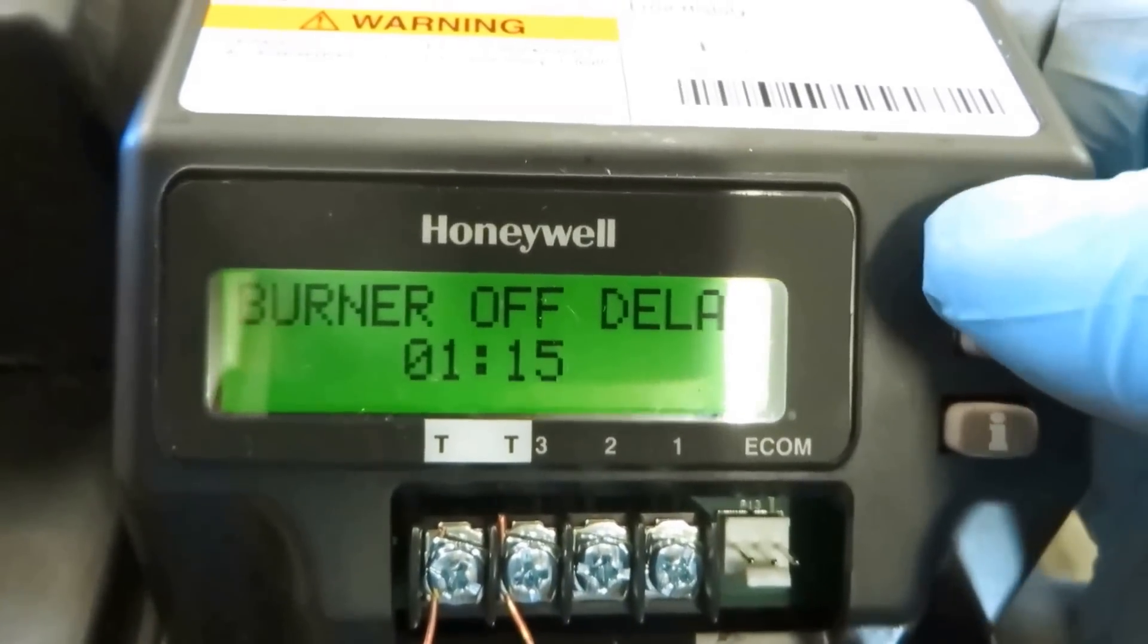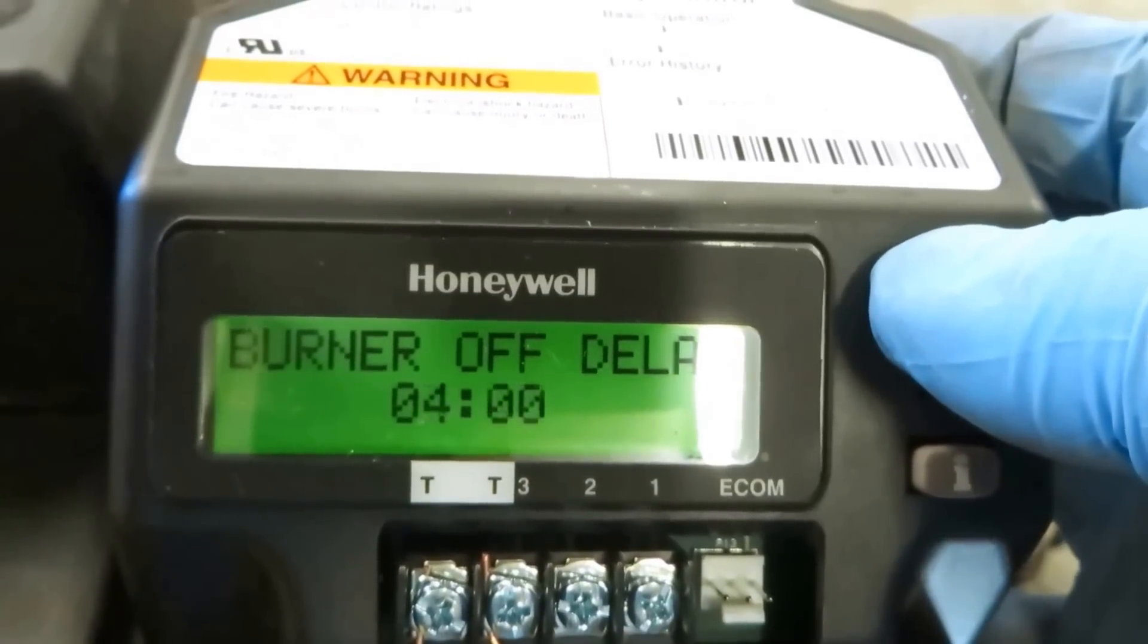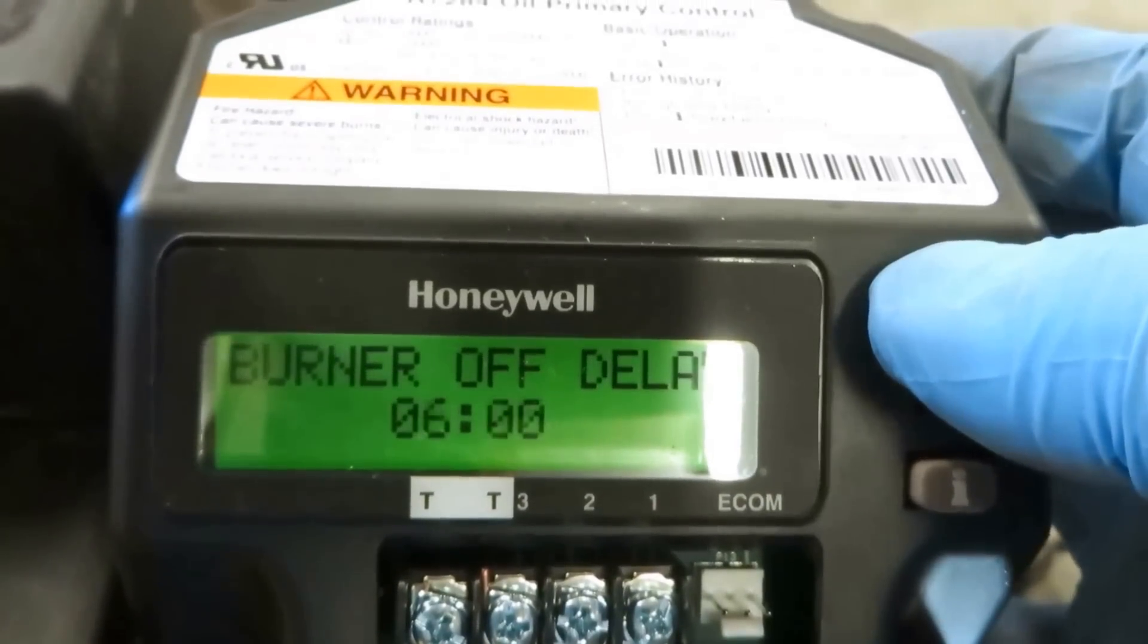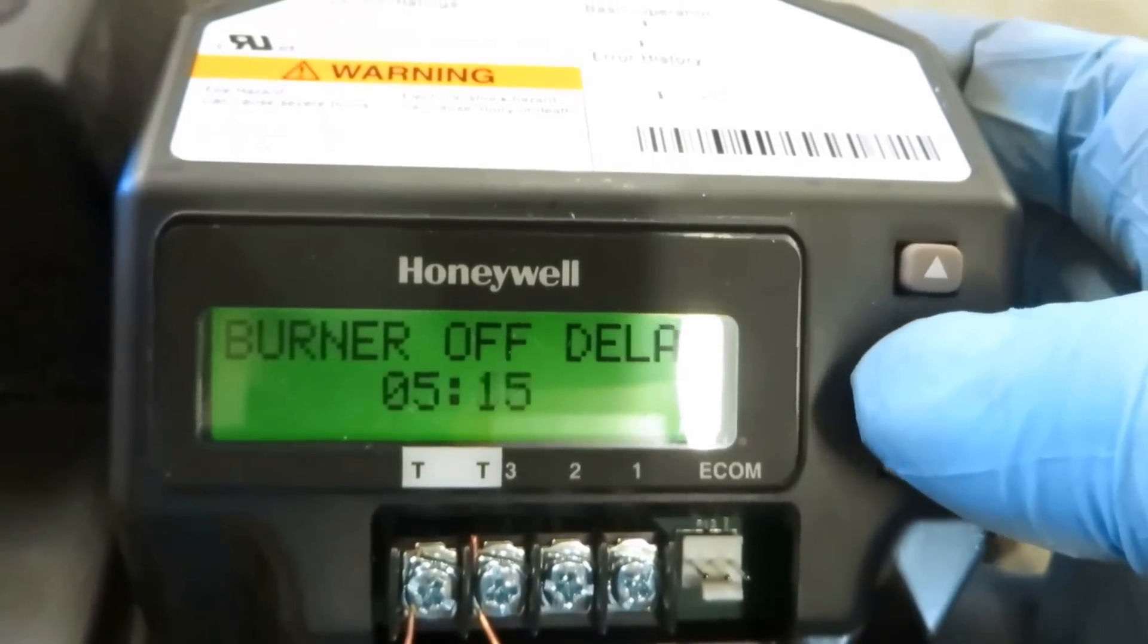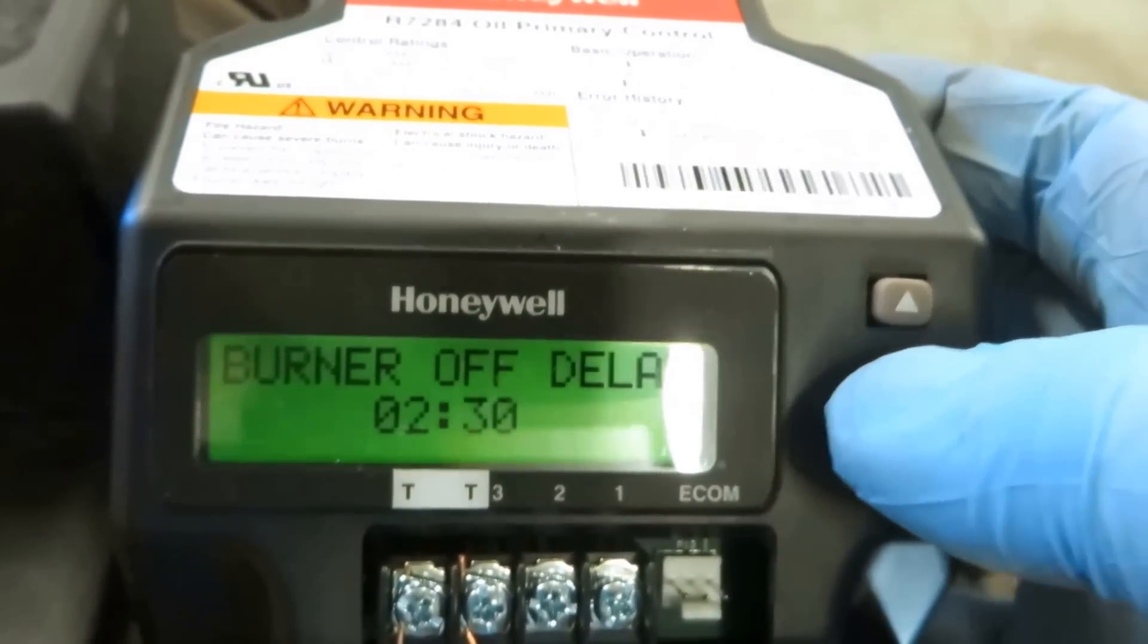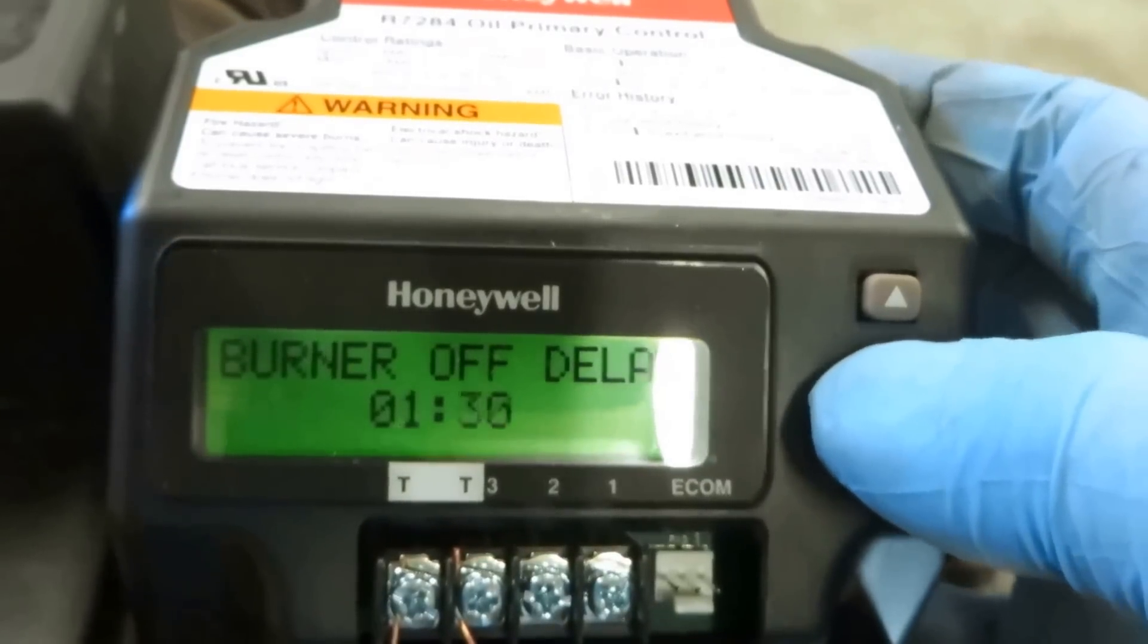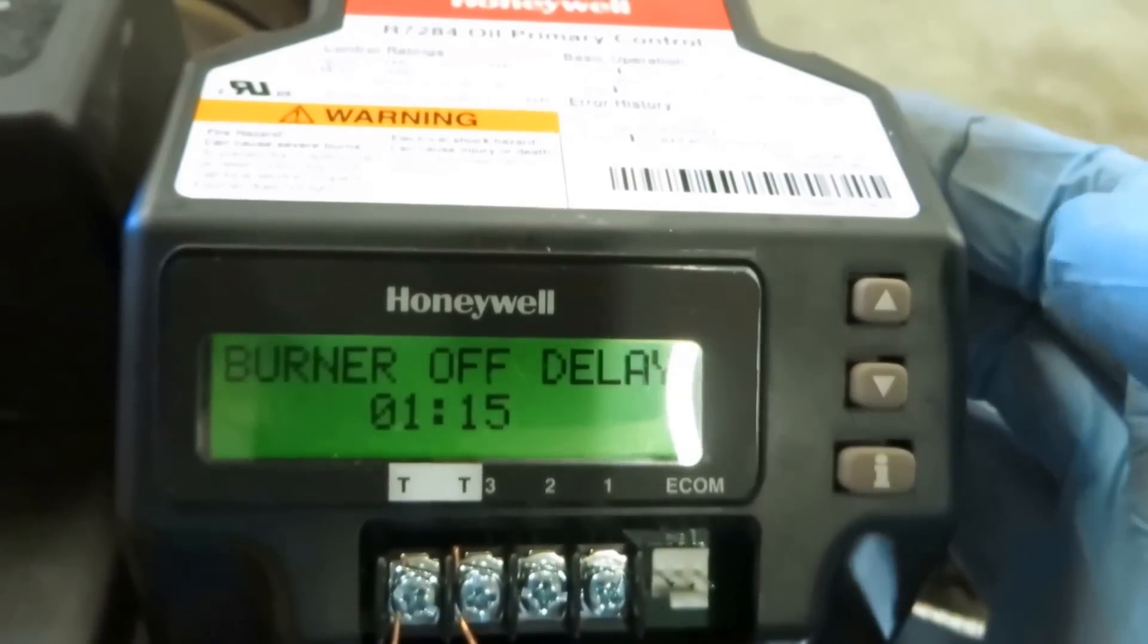I can go up as high as I want. That's the post purge. Let's see how high it goes. It can go way up. Post purge somewhere around, even three minutes is good. That's a long post purge. Depends on the setup. I just had it on 30 seconds. About a minute I guess is good.